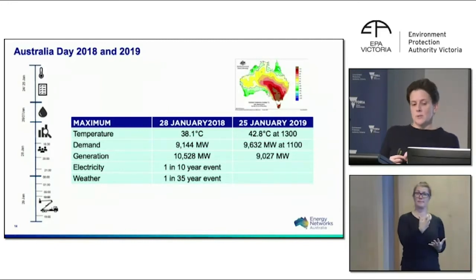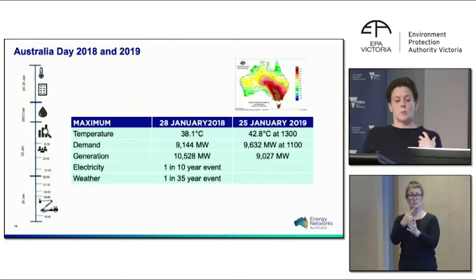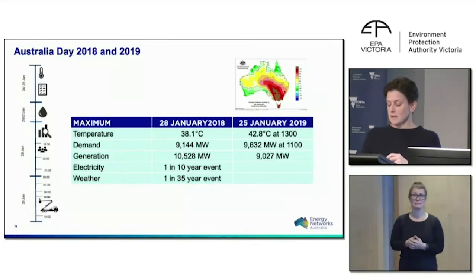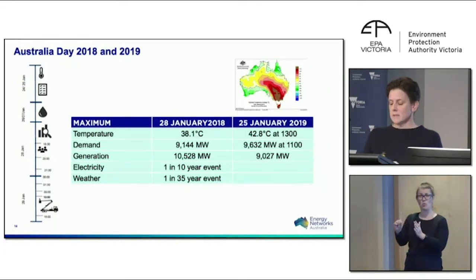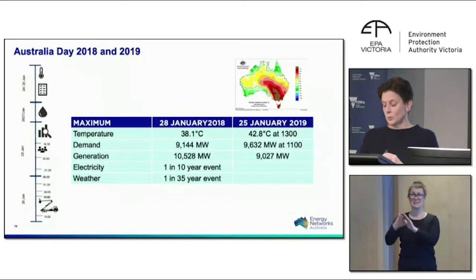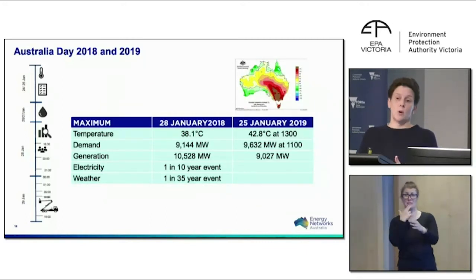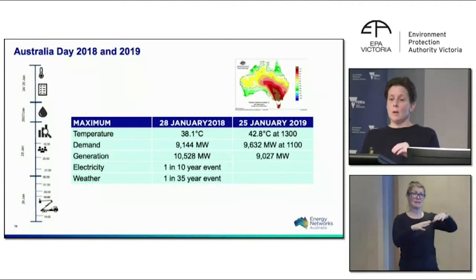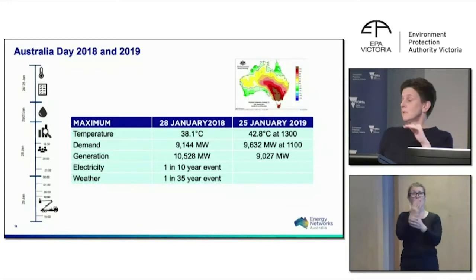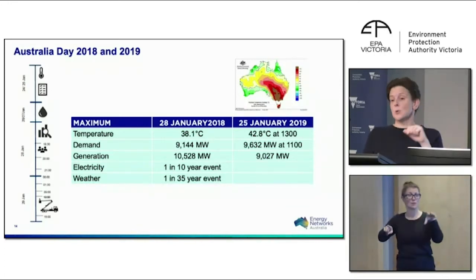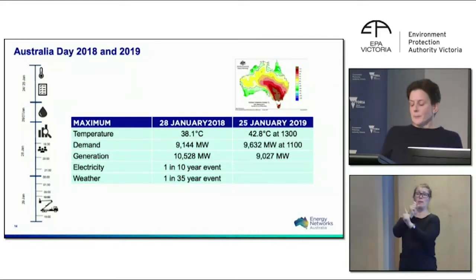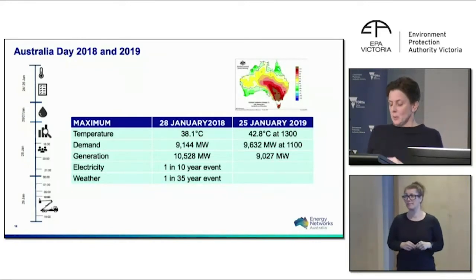On the 25th of January 2019, again it was extremely hot. We had another record for maximum demand, and the problem this time was that we didn't have enough generation. There was an unexpected failure of a power station, which meant the market operator had to direct load shedding, meaning people were cut off in rotation for an hour at a time to ensure frequency remains stable. Because if frequency in Victoria goes bad, it affects New South Wales, it affects South Australia. These events are infrequent, but are likely to become more common with climate change.